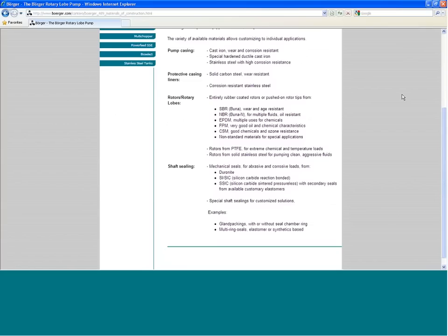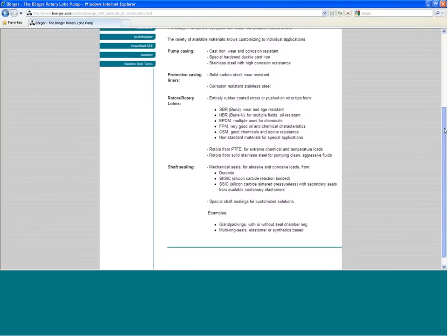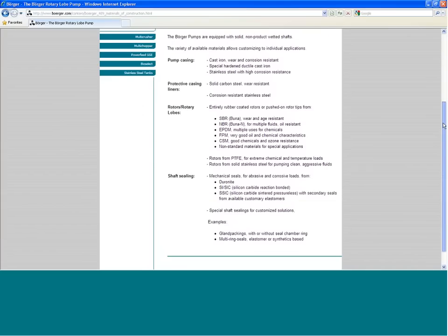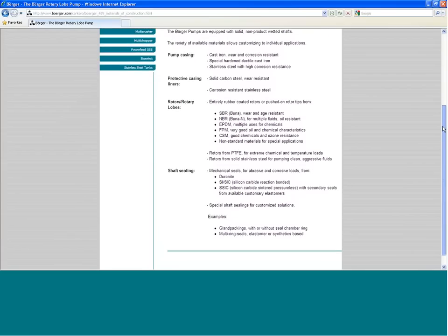And then shaft sealing. Our standard, especially in the water wastewater industry, is a Duronite. It's a lap cast iron seal. It's very robust. It holds up well, and it's a little forgiving for the customer. It doesn't tend to be as brittle as silicon carbide and break.